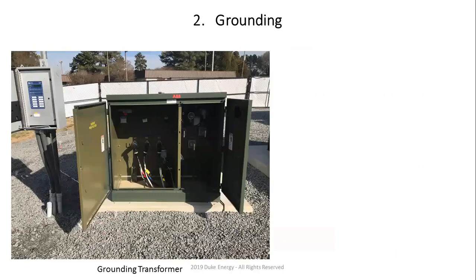Now we have a problem from the protection and control standpoint because when you have that particular configuration, there's no grounded source, right? But when you have synchronous generators, that thing is grounded, right? So that carries all around. If you have a transmission system, the transmission system is delta, and generation sources like synchronous generators are grounded. So outside the generation source, you have a Y grounded delta transformer that is in the switching station. Then transmission is all the way delta, and then when you go to the distribution side, you have a delta Y grounded transformer. So that Y grounded side of that transformer provides the ground for the circuit, right?